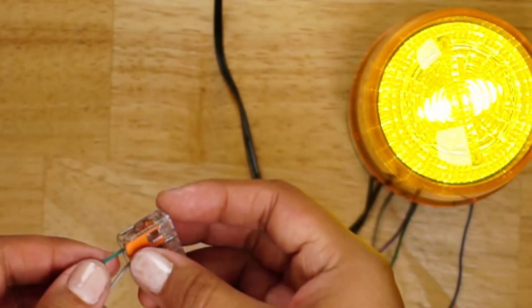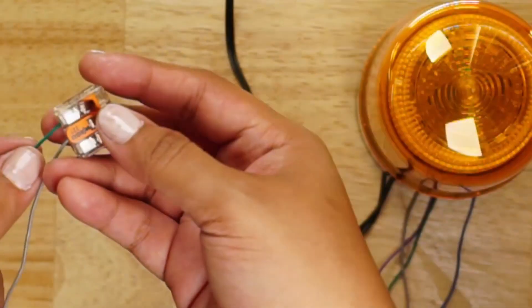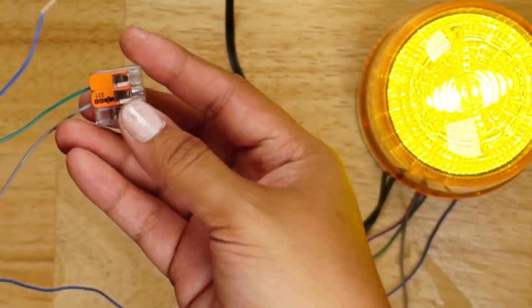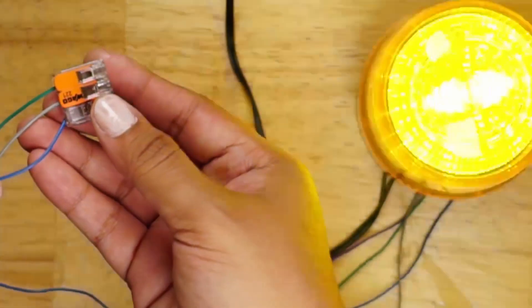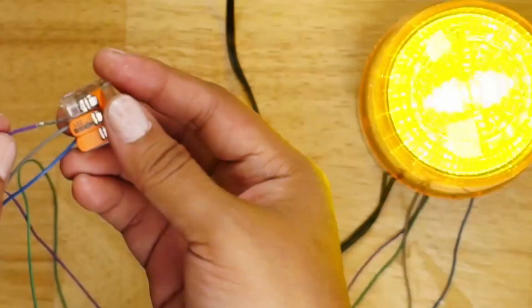Switching to green channel 1, the beacon is continuous lighting. With both channel 1 and 2 connected to common, the beacon flashes at 120 flashes per minute. Adding the purple wire activates the buzzer.